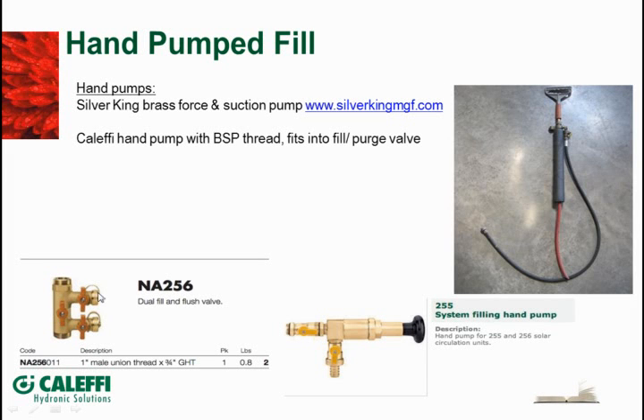So now what you do is you shut that off, and then you can pump your fluid in here. It'll go up through your system, come back down around the system through your tank or through your heat exchanger, and then you can burp the air out of it here. So it's a 3 valve setup. It gives you the way to isolate it and make sure the fluid goes around the direction you want.